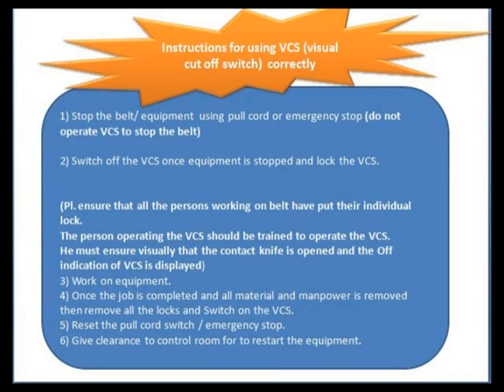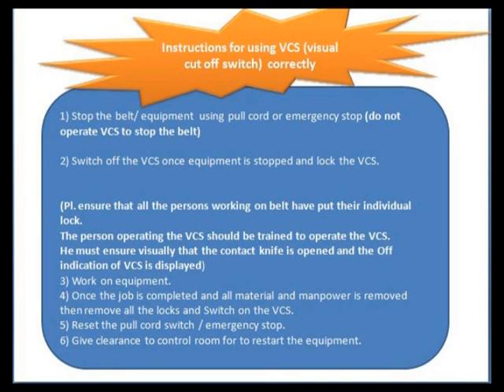After the job is completed, ensure that all material and manpower have been removed, then remove all the locks that were applied on the VCS. Switch on the VCS, reset the emergency button, and give clearance to the control room or central location so the equipment or belt can be restarted. That is all about VCS — thank you for listening with patience.